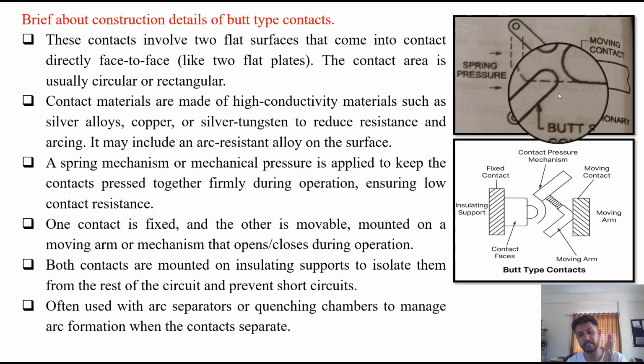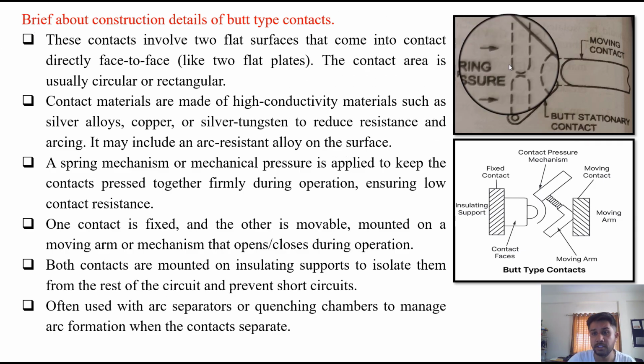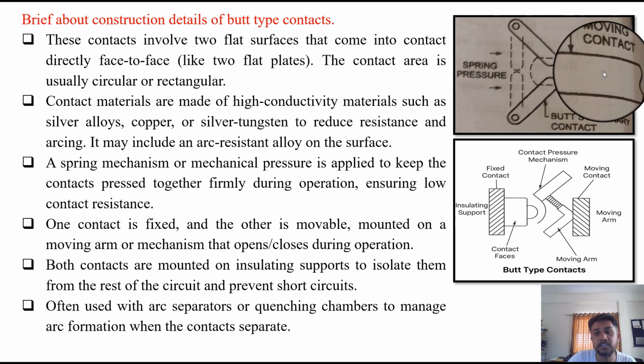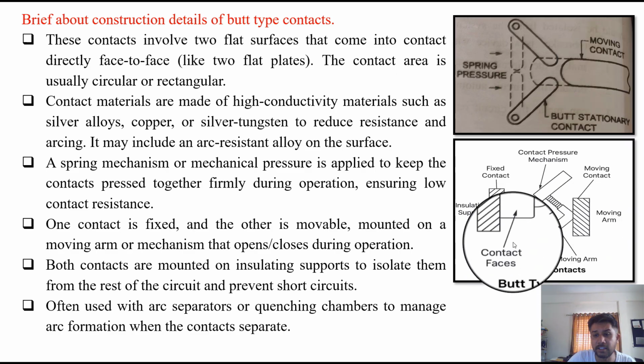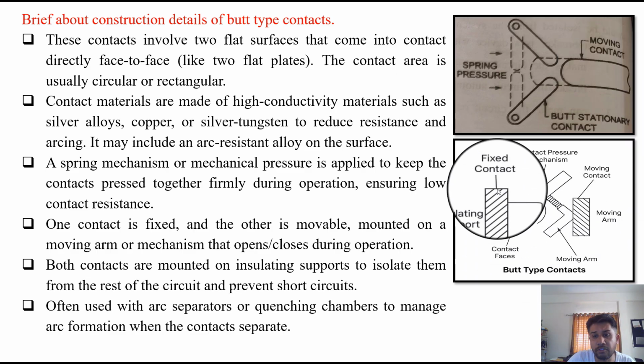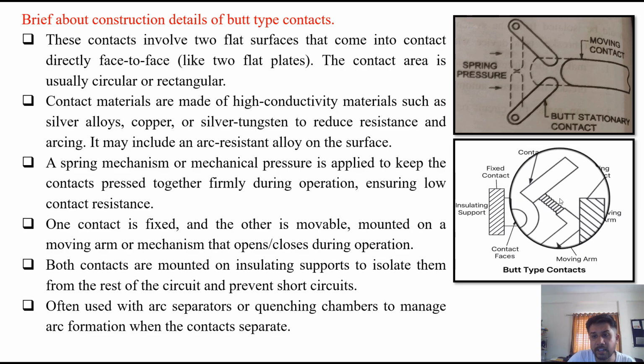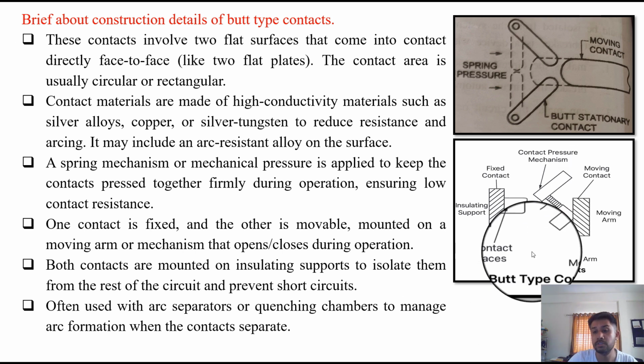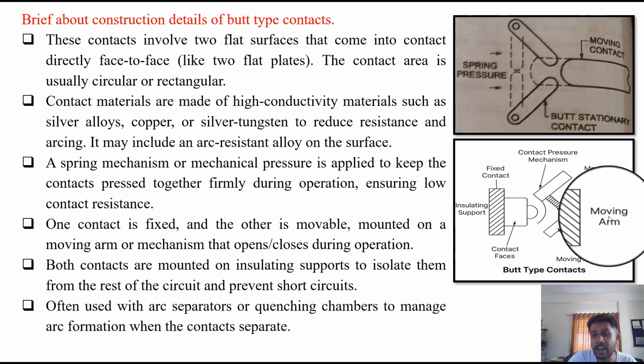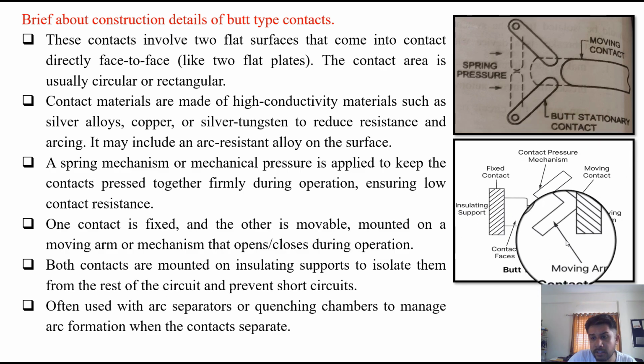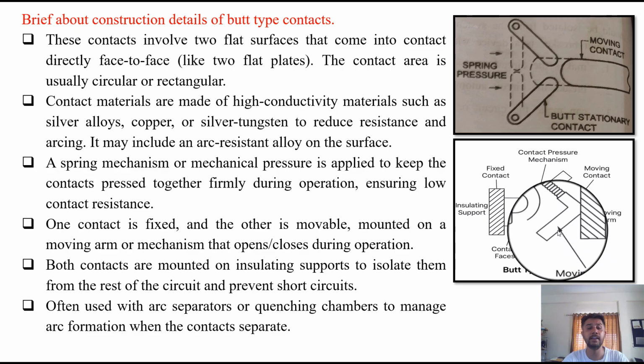One contact is fixed, the other is movable. See this? This is the fixed contact and this is the movable one. So the fixed contact is this, the movable contacts are this. It is mounted on a moving arm or a mechanism that opens or closes during operation. You can see this on the moving arm. So that they can make contact during operation, that is normally closed and opens when any abnormality occurs.